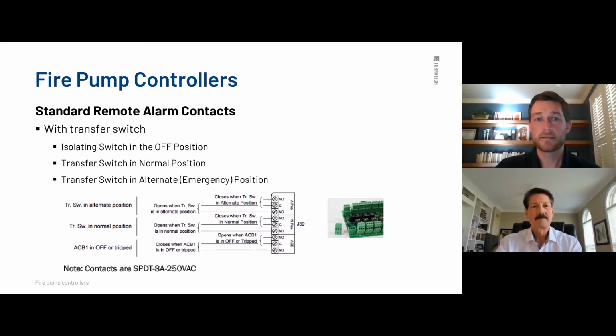And if you have a transfer switch, there's also another bank of remote alarm contacts: isolation switch in the off position, transfer switch in normal position, transfer switch in alternate emergency position. As mentioned before, the ideal position for the transfer switch is the automatic position. If it's not in the automatic position, it's not functioning automatically. Somebody would have to go in there and manually switch it over to alternate and manually put it back over to normal. So if it's in anything other than automatic, you're going to get an alarm. Same with the isolation switch. Like I said before, if the isolation switch is in the off position, your transfer switch is not functional, so you get an alarm for that one as well. And these are set up the same way as the normal contacts on the normal power side.